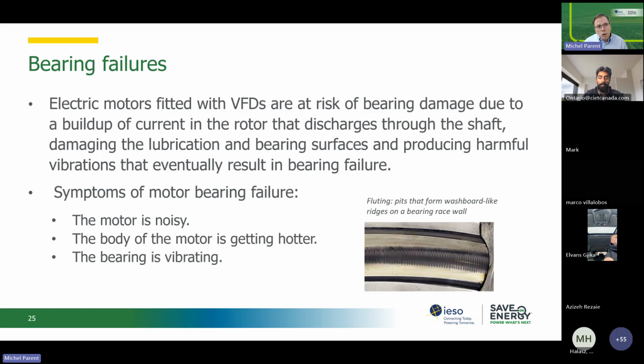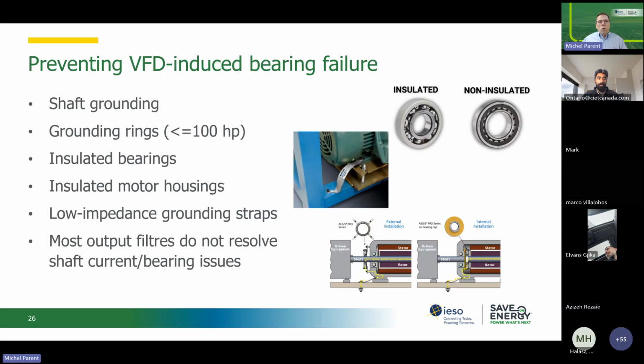What's going to happen is obviously your motor is going to start to get noisy. It's the typical noise we hear from bearing failure, and there's going to be more vibration. In the picture here, you actually see what they call fluting, those little lines that are created in the bearing, and that makes it very noisy. This is due to electricity potential building in the shaft and then discharging through the bearing. The best way to resolve that is usually what we call grounding rings, where you will actually have a ring that goes around your shaft that will be grounded, and it will take care of this voltage buildup in your shaft. Instead of going through your bearing, it will go through basically this grounding loop.